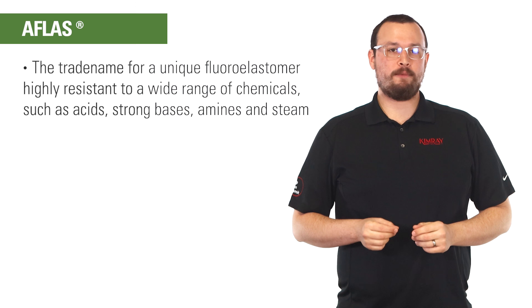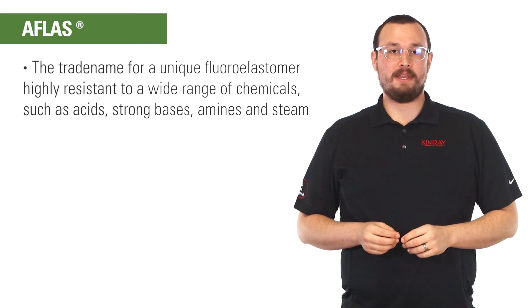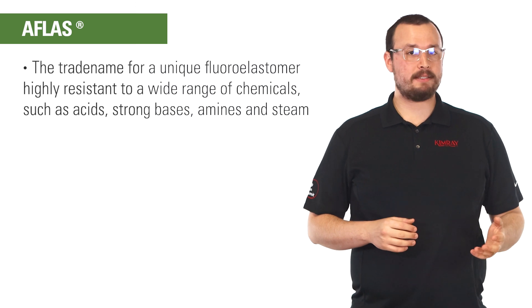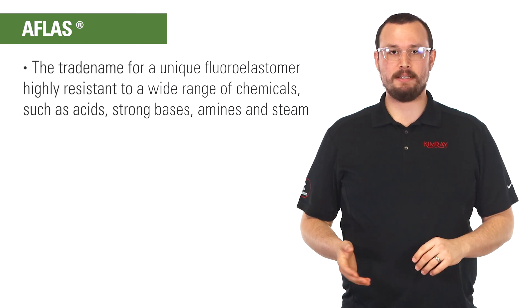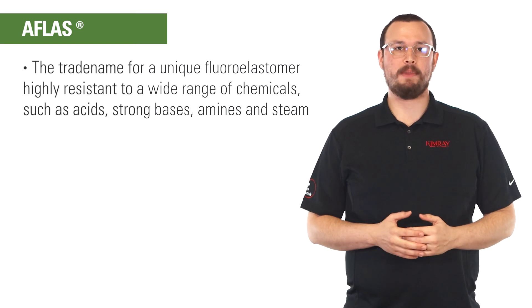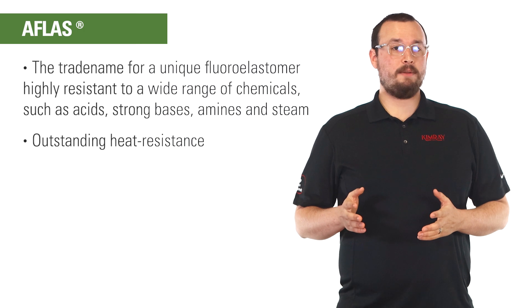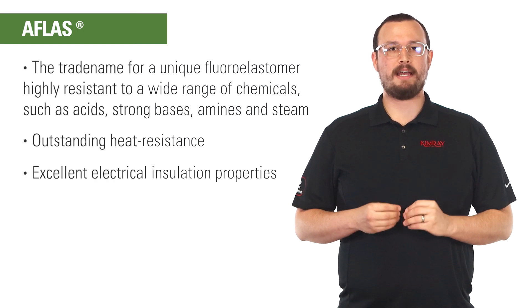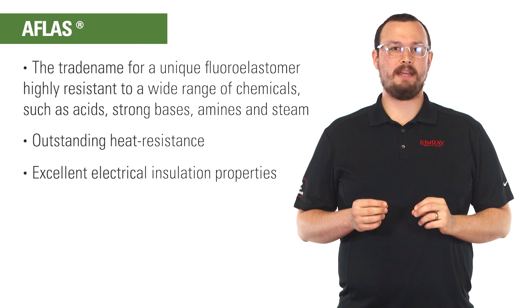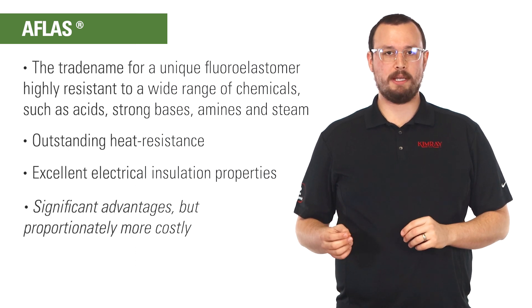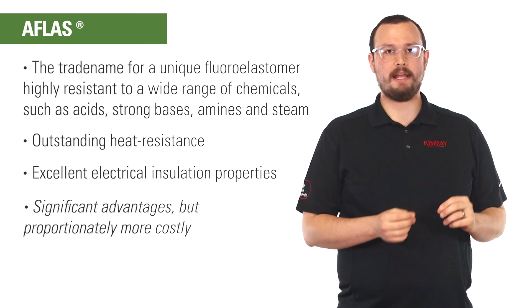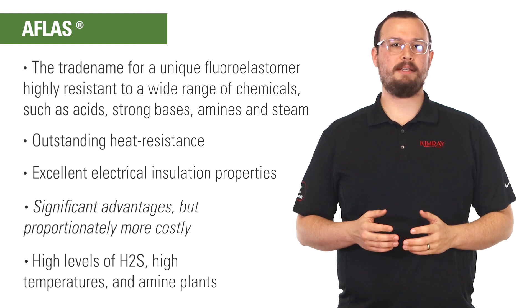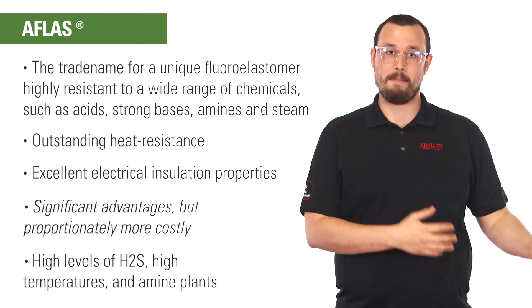AFLAS is the trade name for a unique fluoroelastomer that is highly resistant to a wide range of chemicals such as acids, strong bases, amines, and steam. With outstanding heat resistance and excellent electrical insulation properties, AFLAS has significant advantages but is proportionally more costly. It's targeted at special applications such as high levels of H2S and high temperatures in amine plants.